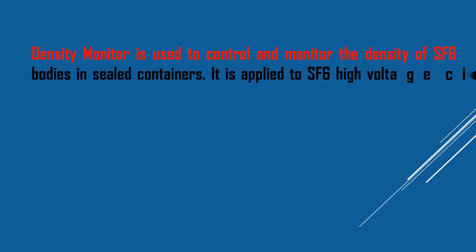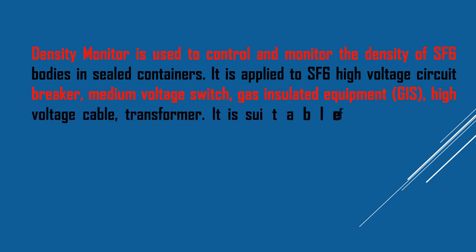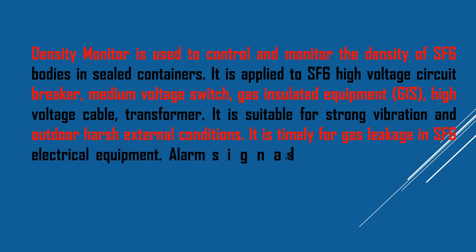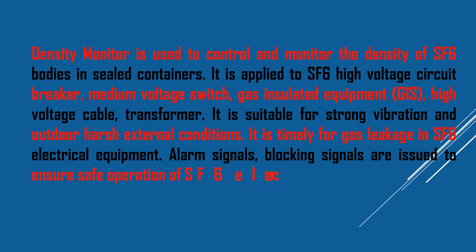The density monitor is used to control and monitor the density of SF6 gas in sealed containers. It is applied to SF6 high voltage circuit breakers, medium voltage switches, gas insulated equipment (GIS), and high voltage cable transformers. It is suitable for strong vibration and outdoor harsh conditions. It provides timely alarm signals and blocking signals for gas leakage in SF6 electrical equipment to ensure safe operation.